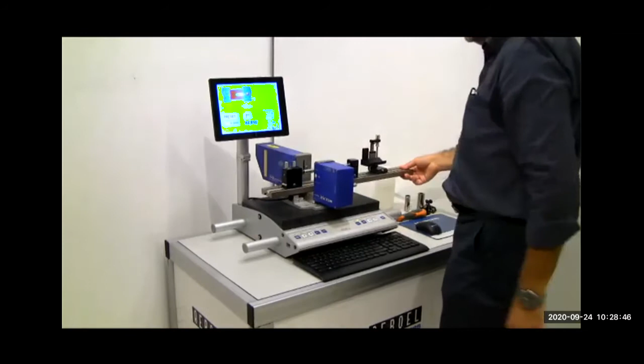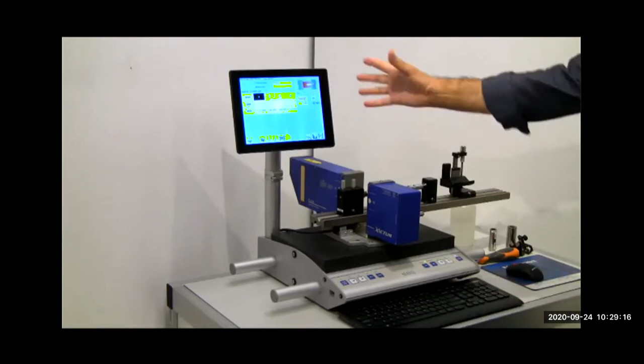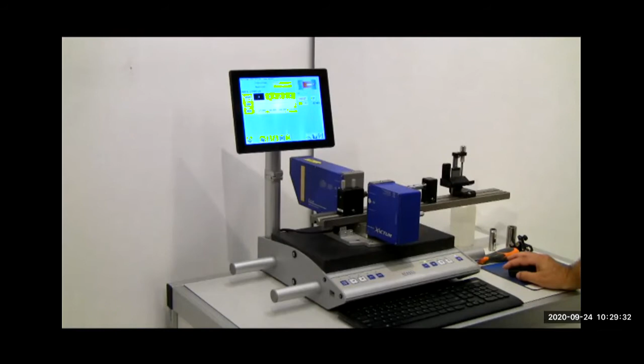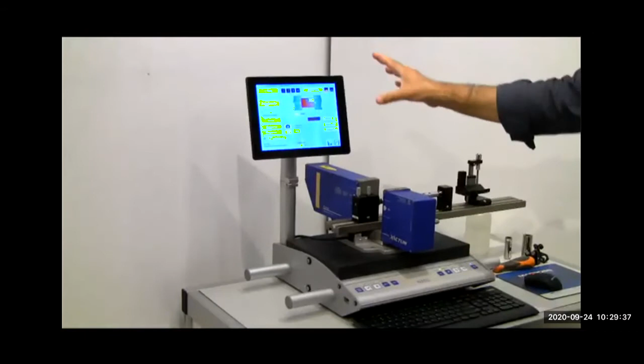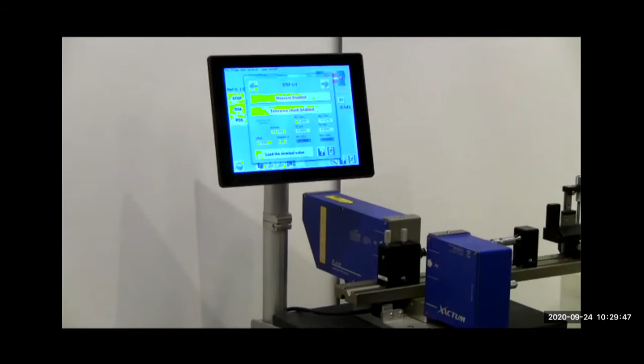In the base, there is a PC card that gives the monitor a normal PC. In this case, there are some menus, like the setup, where you can set up a lot of parameters and so on. We can see the measurement directly, and you have a screen, a window, to program the various types of measurements. You can also program the nominal value and the tolerance and so on.